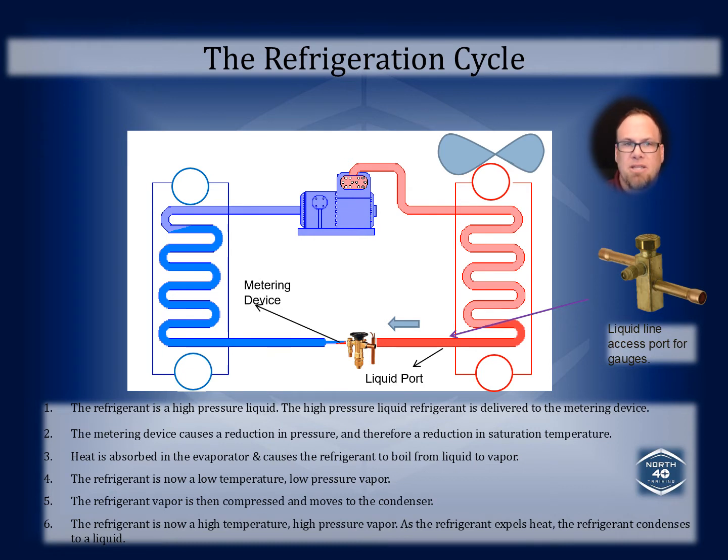And by the time we get to the end of that evaporator, more particularly the last pass of the evaporator, that's the point at which we really should have all the refrigerant in a boiled off vapor form, and that's also consequently what we call the start of superheat. Okay? And that is imperative for us to be starting the superheat at that point. It does two things. First thing that it does, it makes sure that we're using as much of that evaporator as possible to get the most efficiency possible in the application.